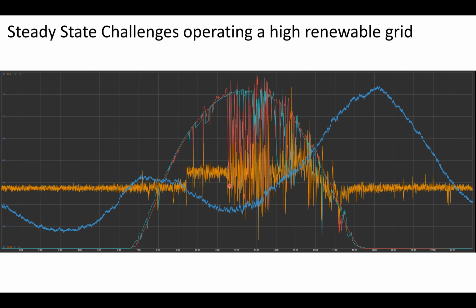that's driving frequency down, synchronous generation kicks in, driving frequency up, and it's a seesaw battle back and forth all day. This was actually pretty good for us. Frequency didn't really go above 60.2 hertz on this day, and below 59.9 on this day. But this is an everyday occurrence for us.